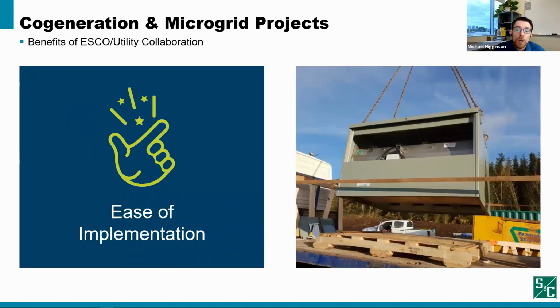One significant advantage of collaboration between the utility, DoD facility, and the ESCO is ease of implementation. Through collaborative efforts, we can choose an interconnection location that makes the process go smoothest for everyone. As discussed previously, these facilities have critical loads that are extremely important to maintain continuous power supply, and there are neighboring loads as well. Through the testing and commissioning process, we often need to test the sequences to confirm we can successfully restore power, which could involve an outage. A well-designed interconnection, paired with an effective test plan, can minimize the outage and its impact to local customers during installation, commissioning, and testing. If we design the interconnection well in collaboration with the local utility, we can minimize these outage durations and their impacts.